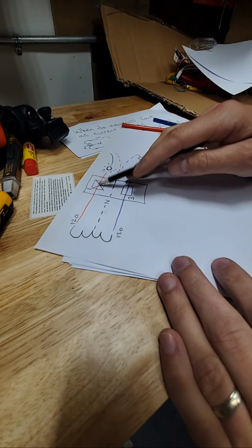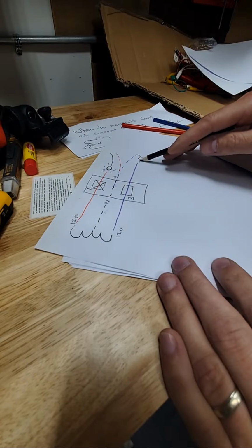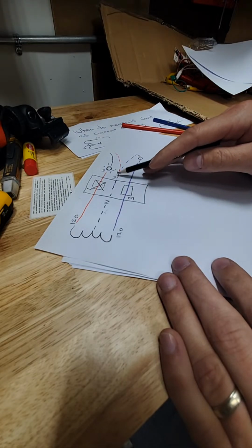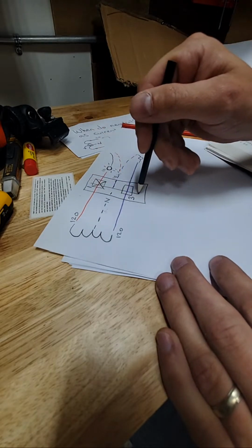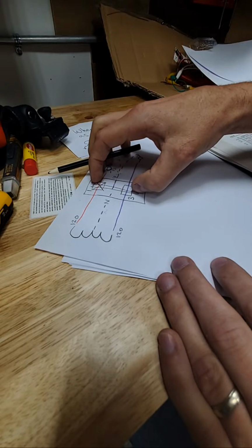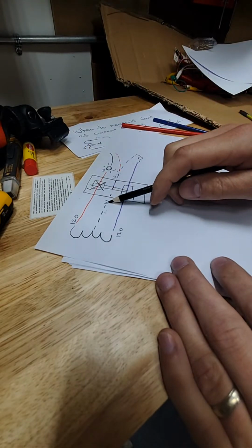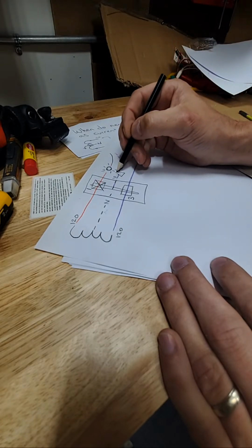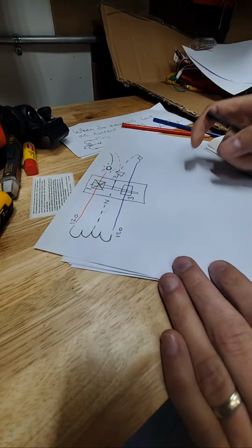So if you turn the circuit off, this is still backfeeding current on the neutral, and electricians get hurt by this all the time. So you got to simultaneously disconnect with the handle tie. That way you shut off both of these. That way if you want to work on this circuit, specifically on the neutral inside of a junction box where there's a wire nut, you can safely do so.